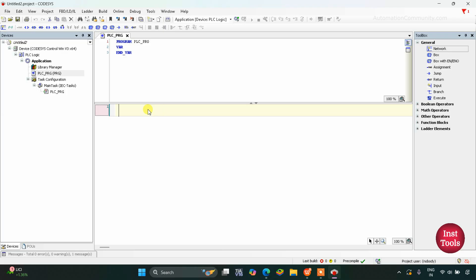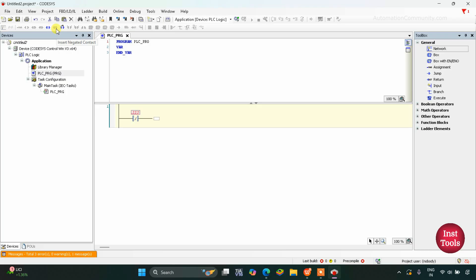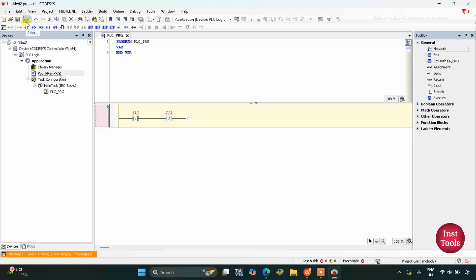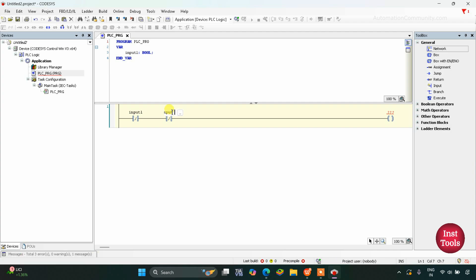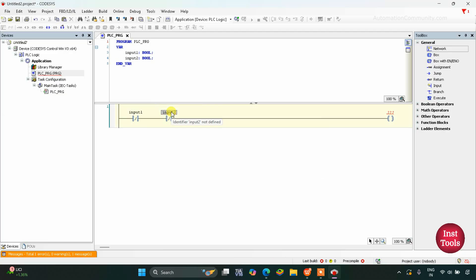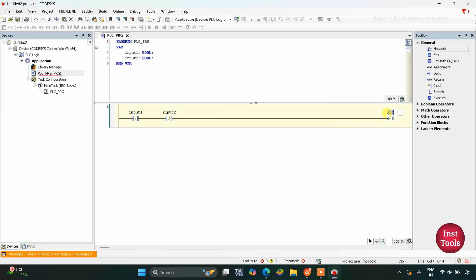To implement the NOR logic gate we will be using normally closed contacts, and these normally closed contacts will be connected in series to implement NOR logic gate. We will insert a negated contact, then one more negated contact, and then insert a coil. This will be Input 1, this will be Input 2, and this will be Output 1.